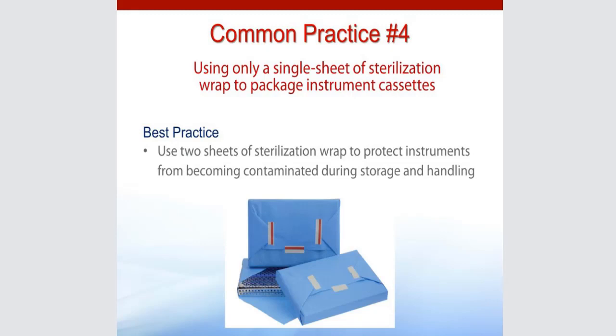Common practice number 4 is using only a single sheet of sterilization wrap to package our instrument cassettes. The CDC and AAMI are very clear, as are the manufacturer's IFUs of these disposable surgical sheets, that we need to use 2 sheets to protect the instruments from becoming contaminated, especially during storage and handling.